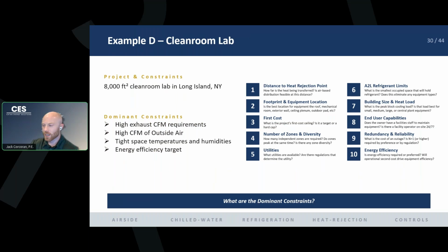Example D, we have a clean room lab, right? It's 8,000 square feet, so relatively small, but these clean rooms and labs have high exhaust CFM requirements, right? All these other examples were dominated by the code minimum requirements of outside air, but in this situation, if we're pulling out all that exhaust air, we need a lot of outside air to make up for it, right? We want to maintain neutral mass balance. We want to balance our air coming in and air coming out. We're going to have a lot of outside air relative to return air in this situation.